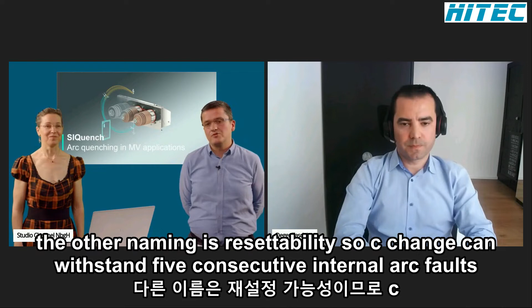Kerem, you can reflect the details, but reusability - withstanding up to 5 consecutive full fault currents - is the main benefit you may reach with the Siemens SIQuench solution. That's right. Compared to the competition, our unique feature is reusability, also called resettability. So SIQuench can withstand 5 consecutive internal arc faults with the full rated current of the switchgear.